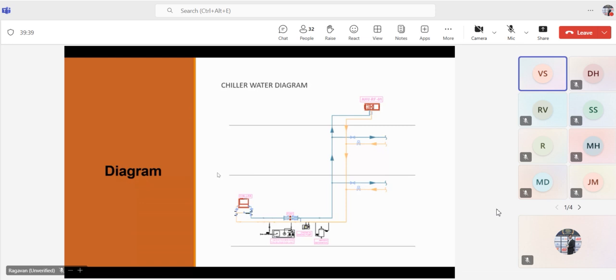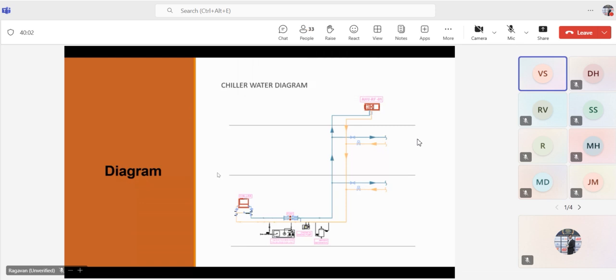pressurization unit. The pressurization unit accommodates the changes in the water volume due to the temperature fluctuation, maintains the system pressure and prevents damage from thermal expansion. It also helps to remove the air from the system. Then the next one is the air separator. The air separator removes the air from the chilled water, preventing airlock and improving the system efficiency.